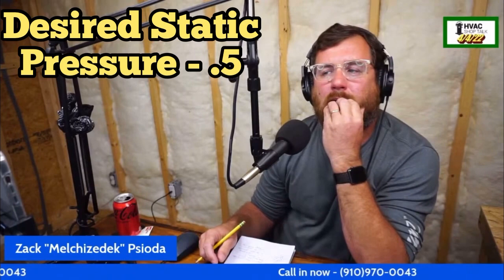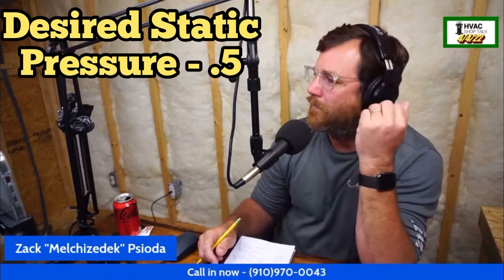Basically, in a nutshell, ECM blower motors dropping out. This is a motor and module already replaced last August. So at that point, I've got to put my thinking cap on and dig deeper and measure total external static pressure, bouncing between 0.71 to 0.75 inches water column, fully engaged second stage compressor. I looked up blower charts for that particular half horsepower. They're recommending about half-inch water column, what they're going to see on that one.